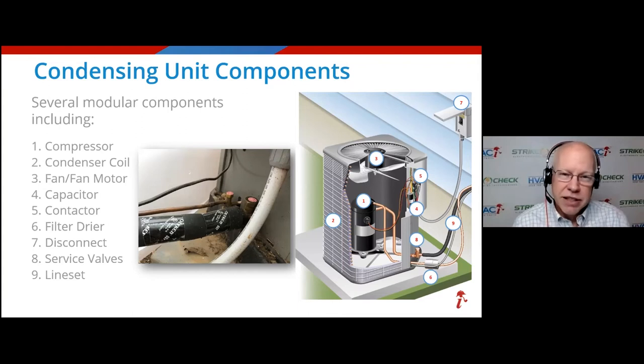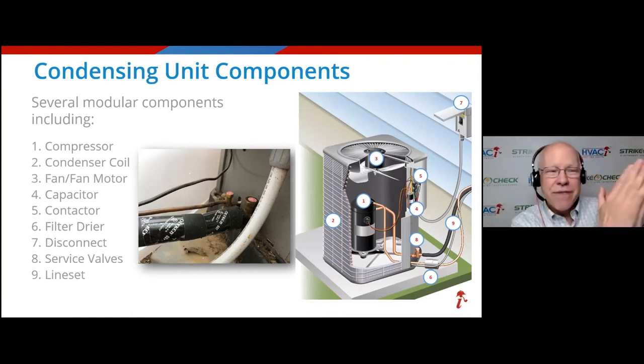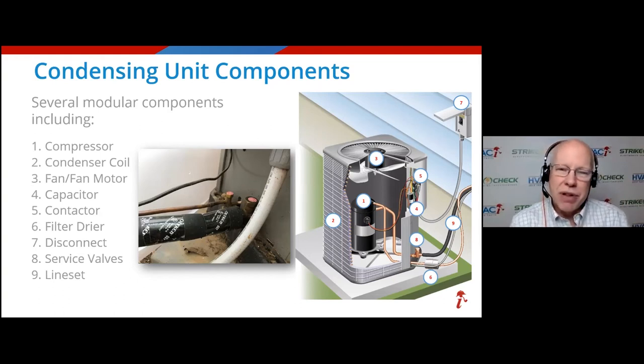You know what? That's not gonna happen. They're gonna fix the copper pipe at the leak. They're gonna cut out the section that's damaged and put a new section in. Same thing applies for line sets. When the line set gets damaged, you don't put in a new line set. That's $600 or $700, depending how long it is and where it goes. You fix it in most cases. So keep that in mind.